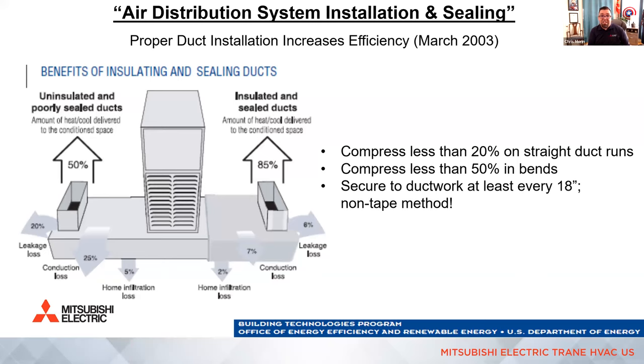So really easy on poorly sealed and poorly insulated ducts to lose half of the capacity on a furnace or an AC system. It's crazy how bad it can be out there. And you can see just 20% leakage, 25% conduction losses because people are still putting ductwork in attics. And then just 5% for infiltration because we're depressurizing different spaces. And we could lose 50% of what that system was trying to do for the home. But if we seal and insulate it correctly and we have minimal losses, minimal conduction losses, or none because it's within the building, we can really improve the performance of the system. And actually, if it's a new system, install a smaller unit, right?